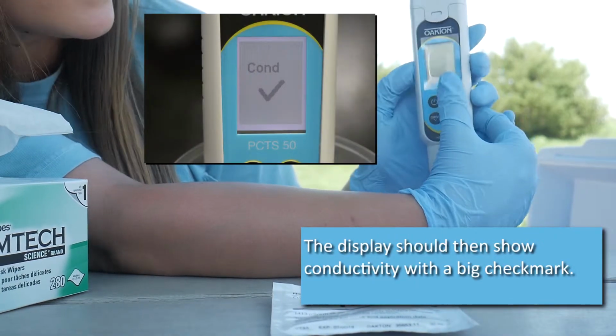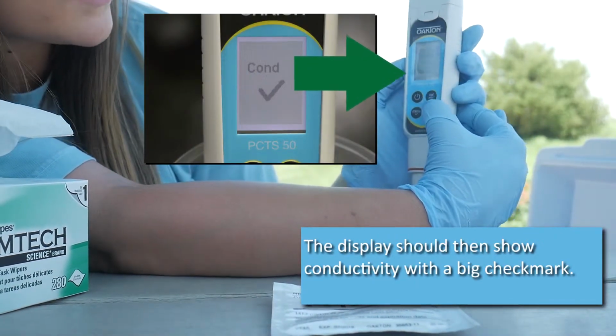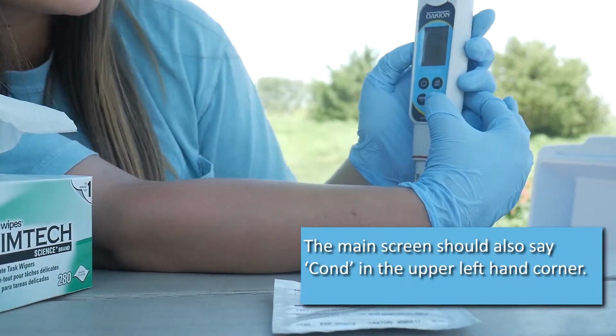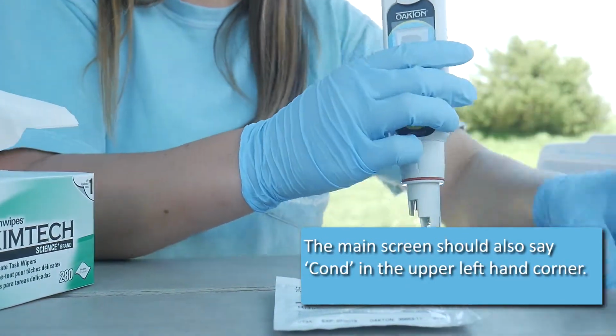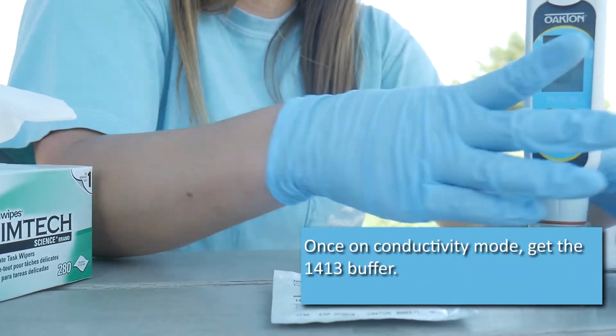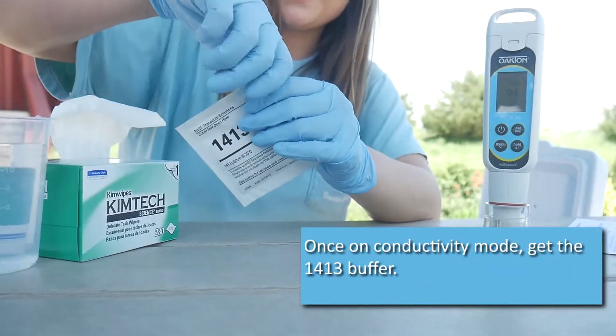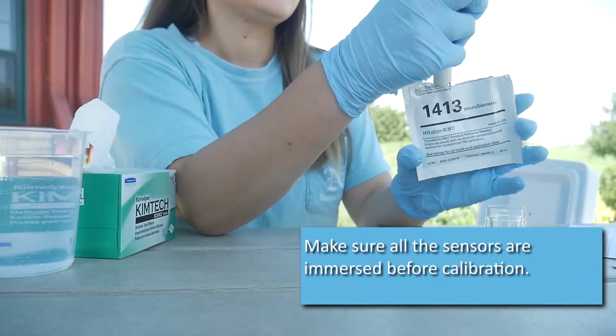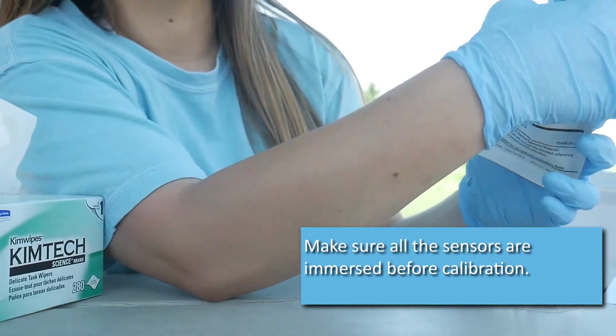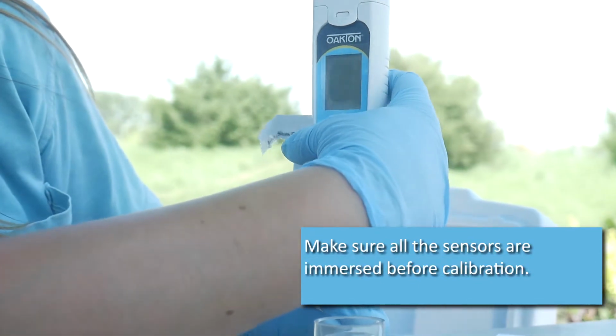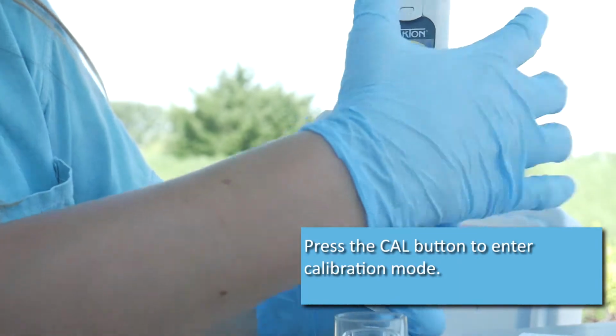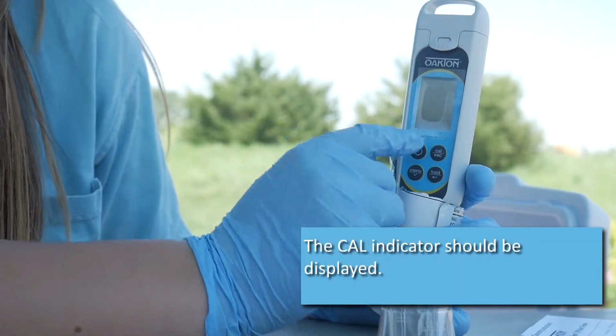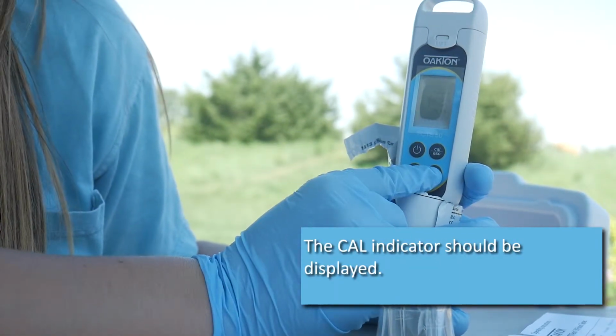The display should then show conductivity with a big check mark. The main screen should also say Cond in the upper left corner. Once on conductivity mode, get the 1413 buffer. Make sure that all the sensors are immersed before calibration. Press the Cal button to enter calibration mode. The Cal indicator should be displayed.